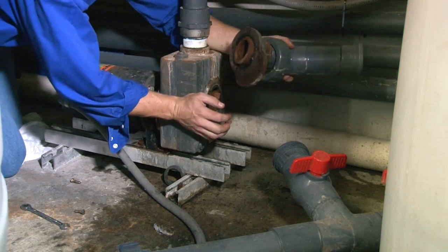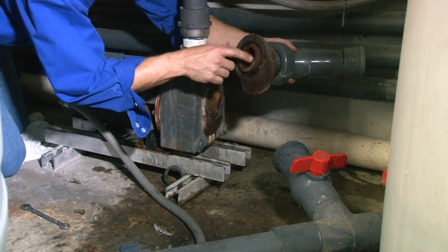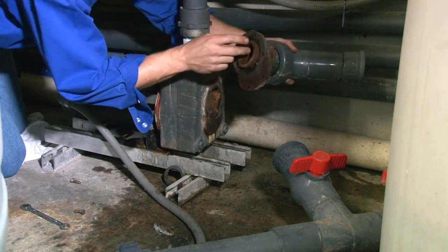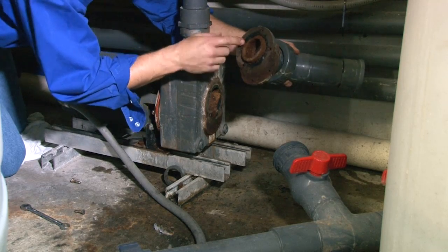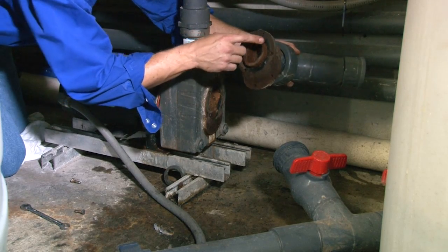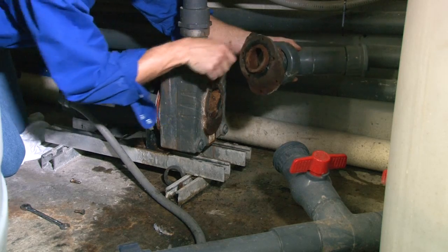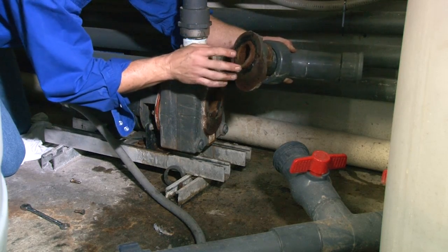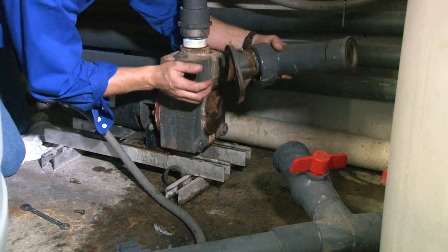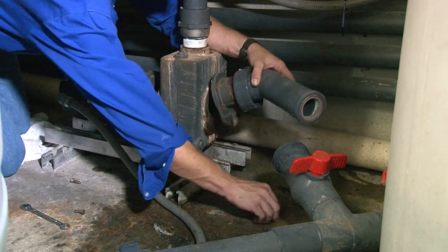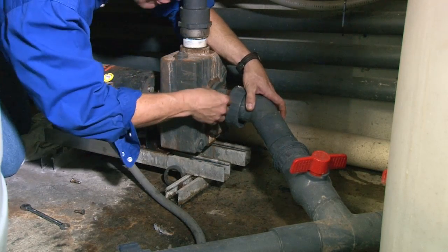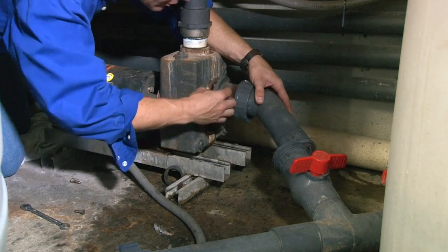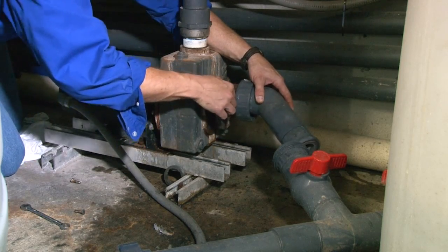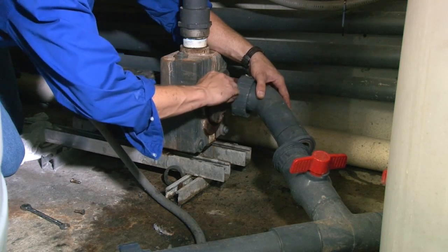By the way, if you happen to pull this inlet open and you see a rubber flapper valve on here, it should be removed. So if you happen to see a rubber flapper valve on the end of the pump, just cut the flapper out. With a razor knife, you can cut the flapper out of it. The flappers tend to fall off as it wears out and actually will clog the impeller at some point. So likewise, when you're buying a new pit pump from us, make sure you pull that flapper out before you put it into service.